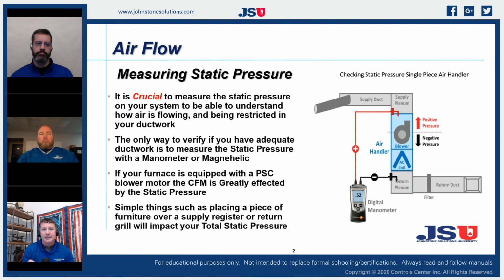With an electric furnace, it's a little bit different scenario because it has the coil already assembled as part of the component, the complete unit, right? So they've already factored in the amount of static drop happening across that A coil. So if I took a half horse blower motor with a 10 by 10 wheel, an exact blower, and put it in a gas furnace, I would have a different airflow chart for that blower than if I pulled that blower assembly out and put it into an electric furnace, because that electric furnace is already adding in that static drop across that coil. So I have a different reference point.